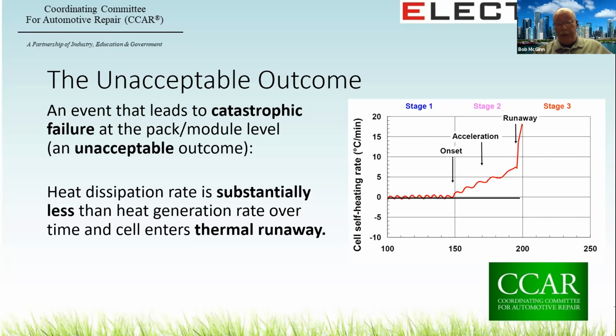And this is described as an abuse event occurs within the cell that leads to an increase in temperature. Pick your favorite mode of failure. Reaction within the cell creates additional heat and gas, and the reaction zone expands. The heat dissipation rate is substantially less than the heat generation rate over time, and the cell enters thermal runaway. Additional heat and gas are produced. The cell vents violently and explodes. And in this case, the adjacent cells are driven to thermal runaway and also explode. Cascade of cell failures consumes the entire battery.